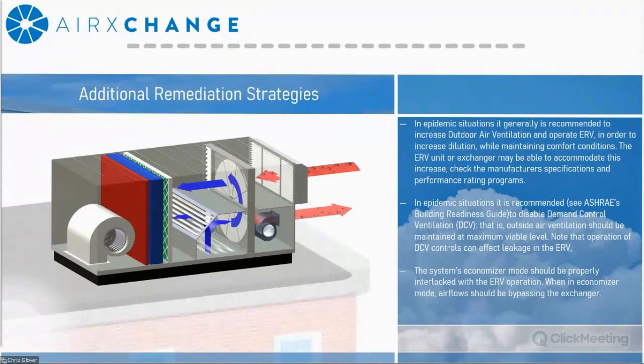And I would like to say that for units equipped with Airxchange wheels, increasing ventilation and filtration may be possible through what we call segment swaps. I'm going to discuss this in a following slide, but once again, be aware of the system effect prior to making that operational change to the system. For ERV systems equipped with demand control ventilation, you want to disable that control. And lastly, for ERV systems equipped with economizer, you should check to make sure that the ERV operation is interlocked with the economizer. It really should be, but you want to make sure that that's the case and that the air is properly bypassing the heat exchanger during economizer periods.